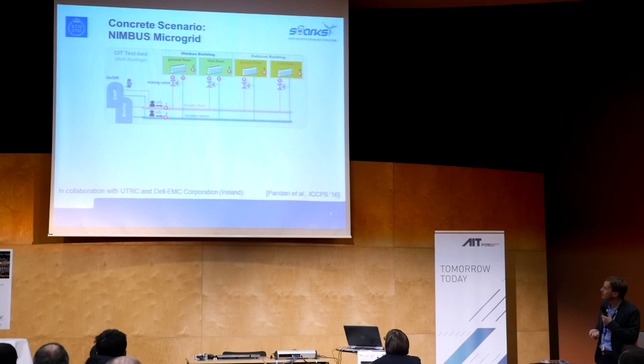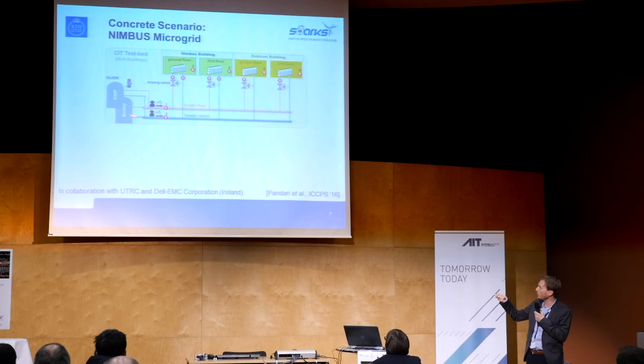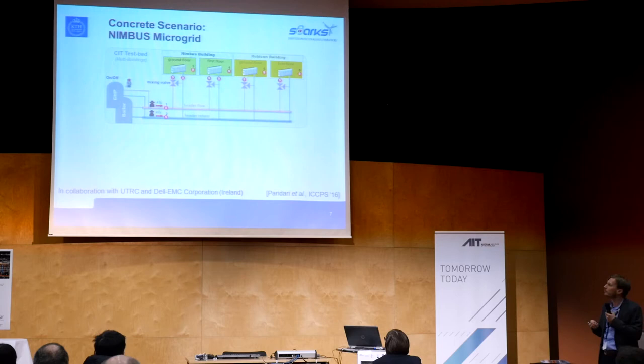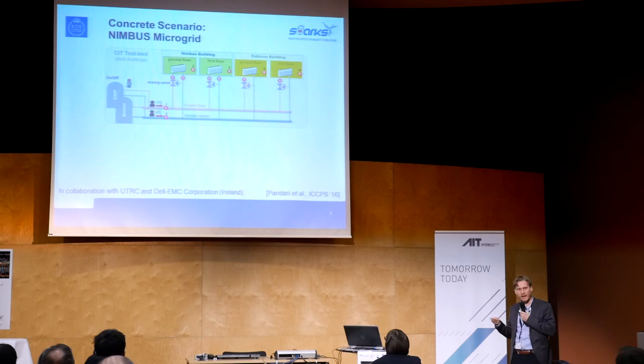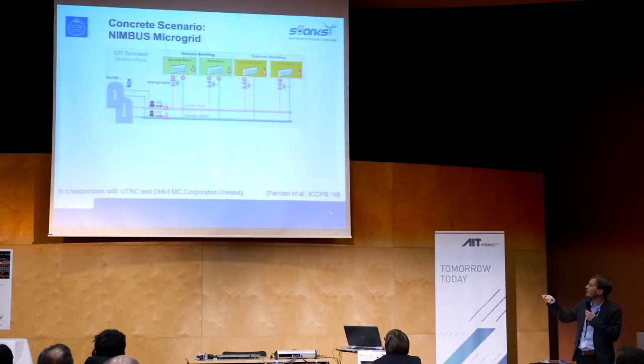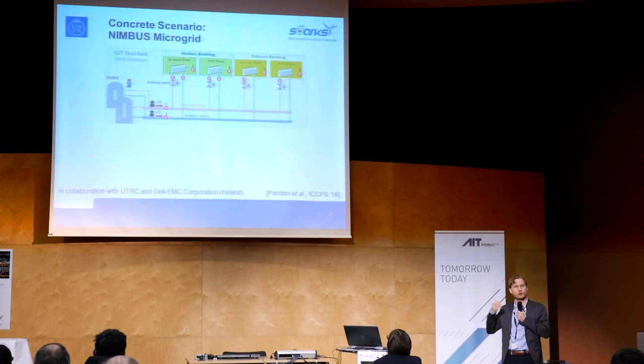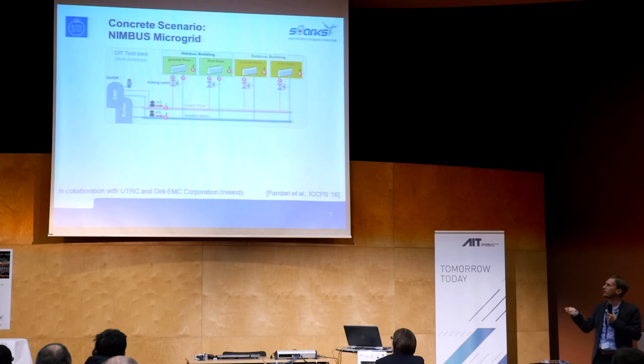This is the Nimbus microgrid — a temperature control system. We have a boiler and a heater here with local controllers that turn the boilers on and off. These were identified as particularly sensitive: they would behave very badly and at high cost if they start to misbehave. We assume that somebody would like to attack these by manipulating the local PLCs, turning them on and off and violating the safety temperature limits. There's a thermal fluid running around in the buildings, and assuming at least one temperature measurement is okay, we can use knowledge of the thermal system to estimate what the temperature should be in the boilers and detect if the boiler control system has been corrupted.